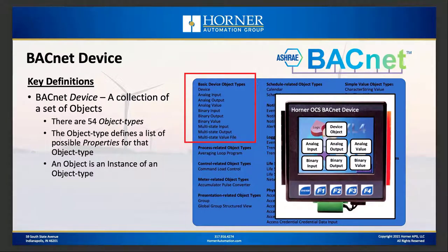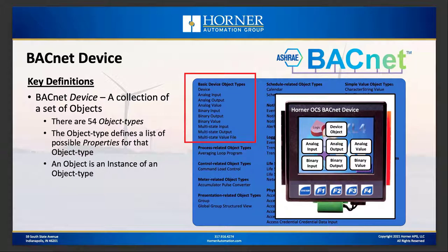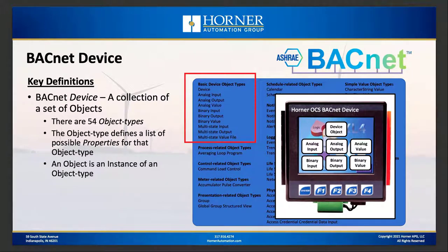There are 54 different object types available, but by far the most common are the basic device object types shown in the red box. The OCS is made up of seven different types of objects: the device object — which every BACnet device must support and reports things like device type and manufacturer ID — plus analog input, analog output, analog value, binary input, binary output, and binary value. You can have multiple instances of each of those six types.